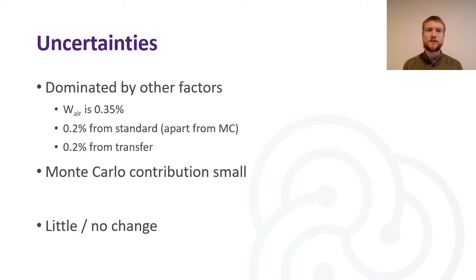So in terms of the uncertainties for the calibration service we perform, the uncertainty is dominated not by the Monte Carlo correction factors, but by other factors. So the W_air value is 0.35% as per ICRU Report 90, but we have already adopted that uncertainty increase. There's also 0.2% from the standard apart from Monte Carlo correction factors, and at least 0.2% from transferring that standard from the free air chamber to the ionisation chamber. So this means the Monte Carlo contribution is quite small, and that will mean there will be little to no change in the uncertainties in the calibration service we offer.